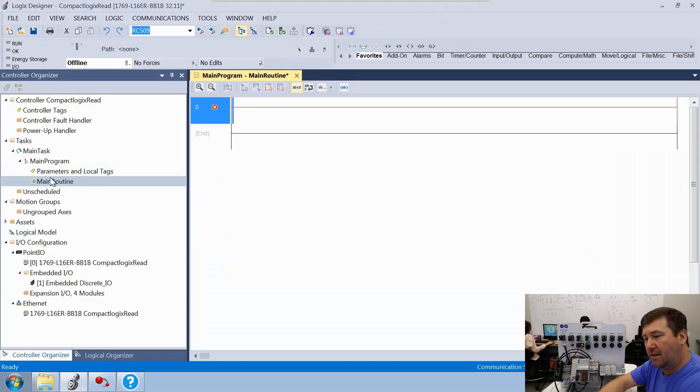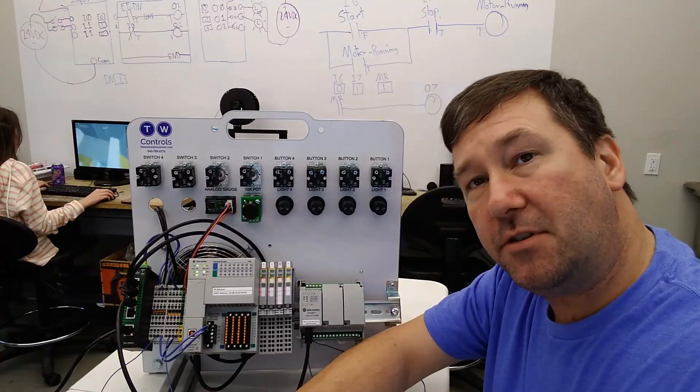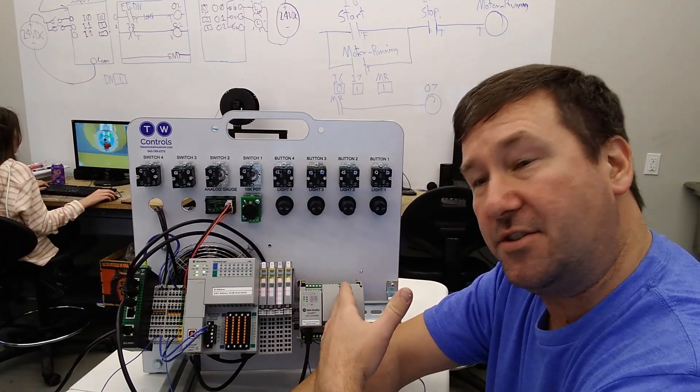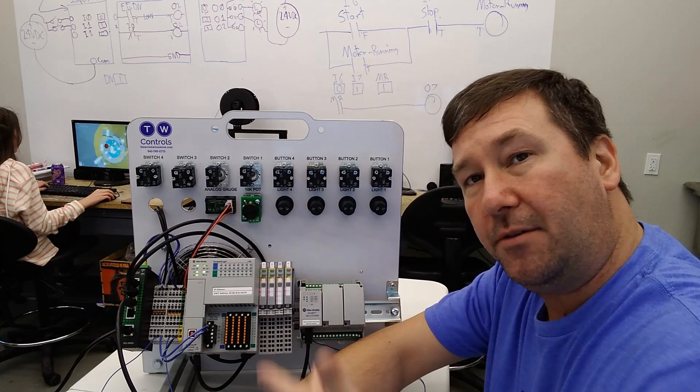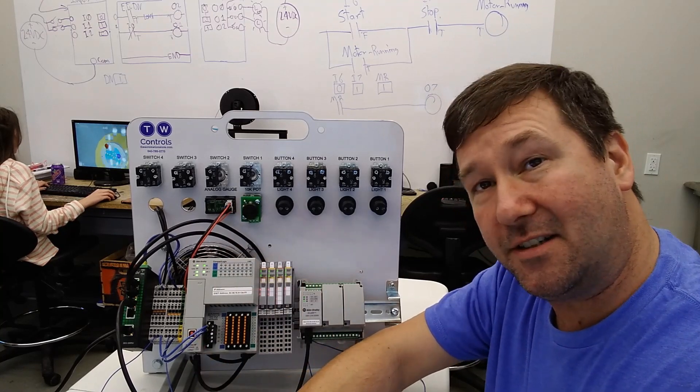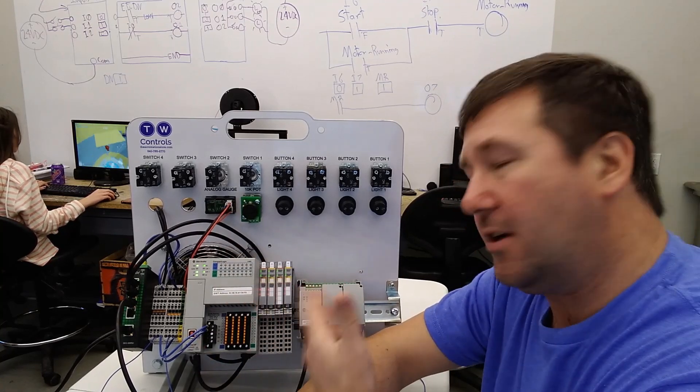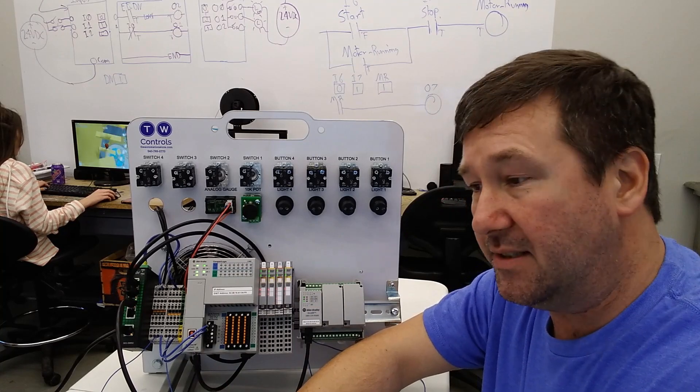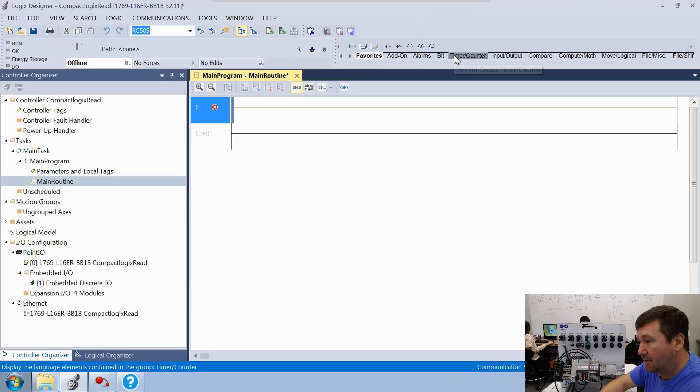So now let's go into our main routine. First, let's set up a timer because we can make this message instruction constantly poll this, but it's probably unnecessary and it's going to tie up bandwidth. Really, we're going to read this once every hundred milliseconds. So we're going to create a timer to start with.